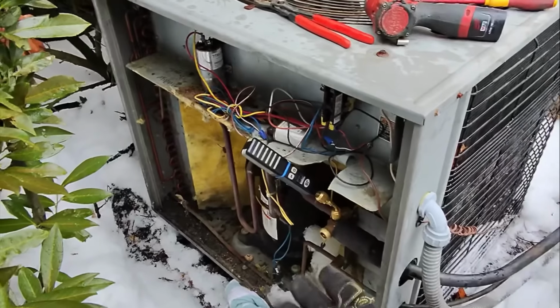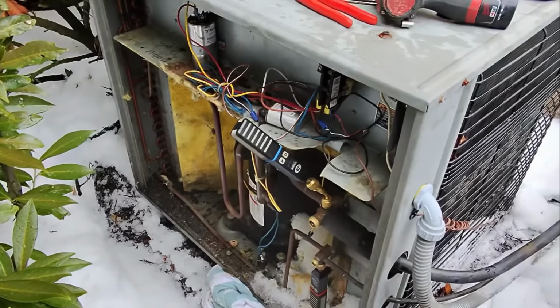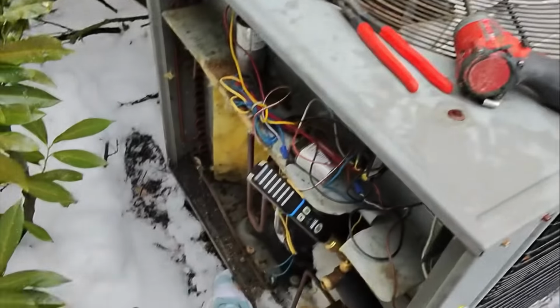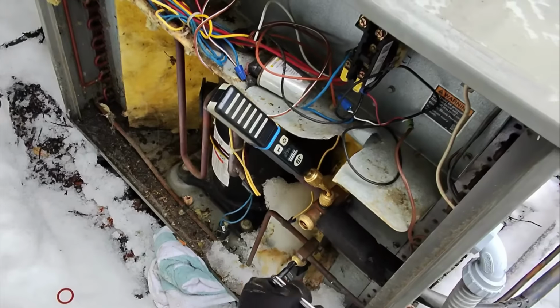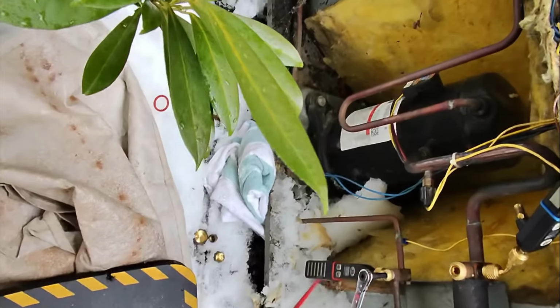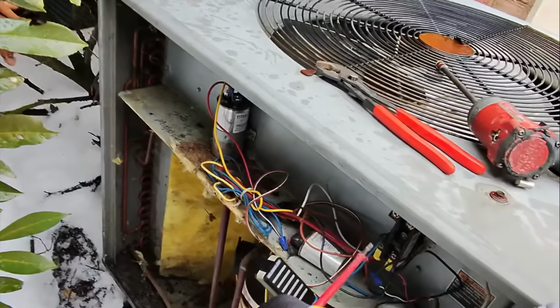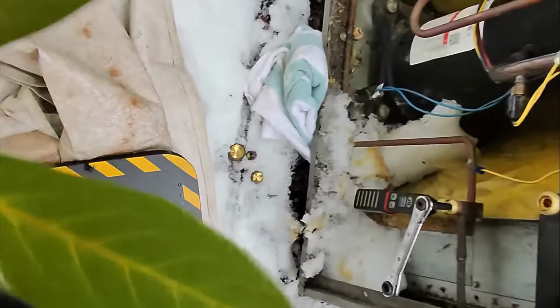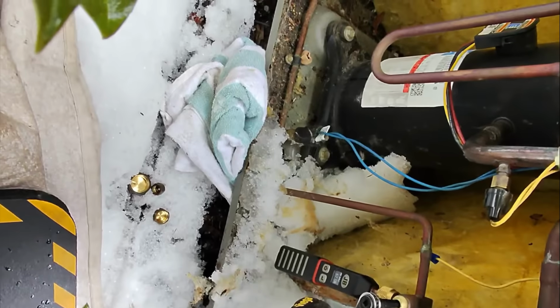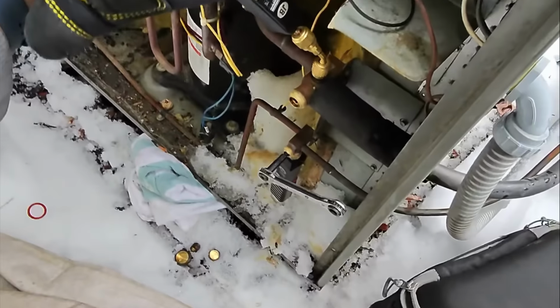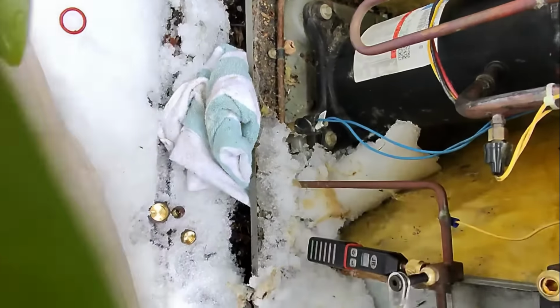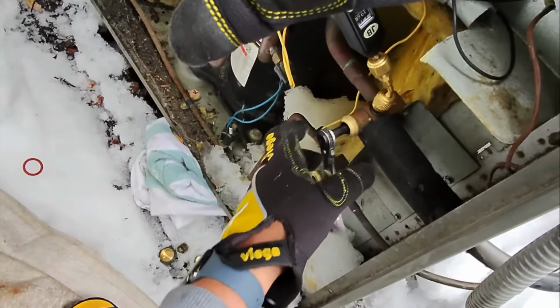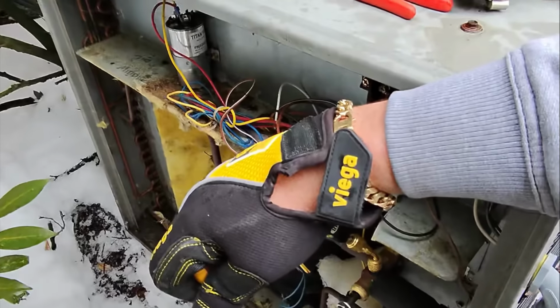Look at that. All right, I'm about to show you a tech tip. We're going to do a pump down of this condensing unit and the refrigerant that's in the system. I have pressure gauges hooked up to my high side and my low side. Let's close our contactor. We're going to watch our high side hopefully drop down, and our low side, we want the compressor to suck in all of the refrigerant back to itself. I have my high side closed. We're going to watch that low side drop.